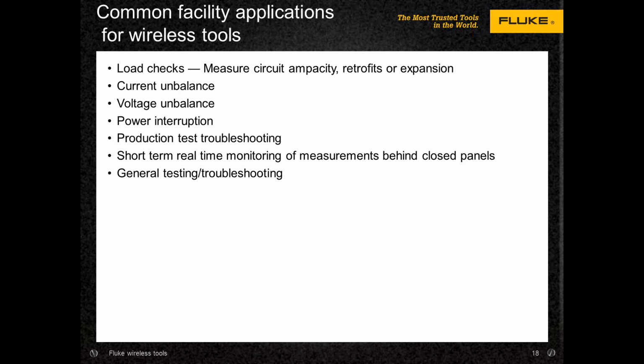So it helps you easily determine whether you can add load or not. If you're going through a distribution panel, let's say, you'd be able to see what your total amp draw is, as well as the branch circuits that make it up. So in essence, you can go to individual pieces of equipment. If you see an overload, or if you see a breaker that appears hot, if you're using thermal imaging or whatever, and it clearly has a lot of current going through it, you can actually go to the consumers and try to determine which one is contributing the greatest amount of current.